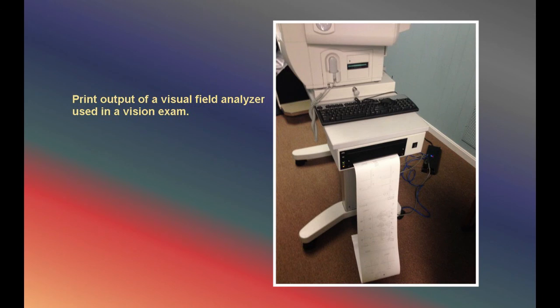Demonstration of PDF Automator. PDF Automator can be used with measurement machines and analyzing instruments. It captures the print data from the print cable and outputs a PDF of the report automatically to a PC display and to a file folder. This upgrades the equipment to paperless status as the printer is replaced in favor of an electronic record. Here is the print output of a visual field analyzer used in a vision exam.